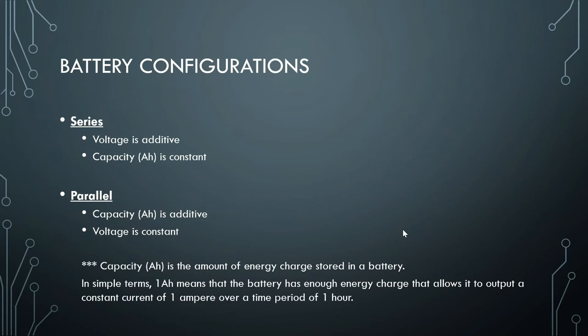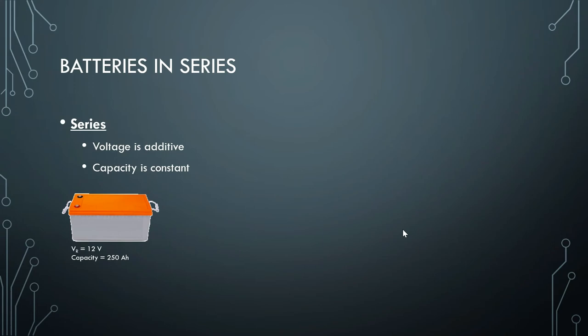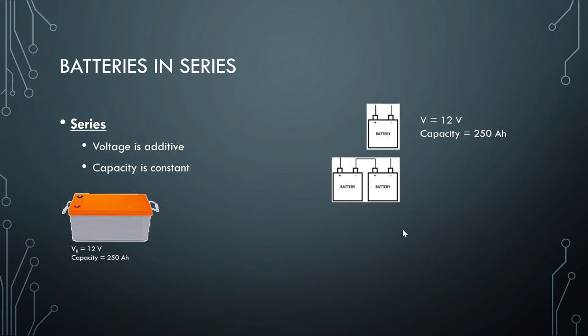Battery in series. As stated, voltage is additive and capacity is constant for batteries connected in series. For example, we have a battery with a voltage rating of 12 volts — measured across the positive and negative terminals — and a capacity of 250 ampere hours. If we connect two of these batteries in series, the voltage is additive: 12 volts plus 12 volts gives us 24 volts output, and the capacity remains constant at 250 ampere hours.